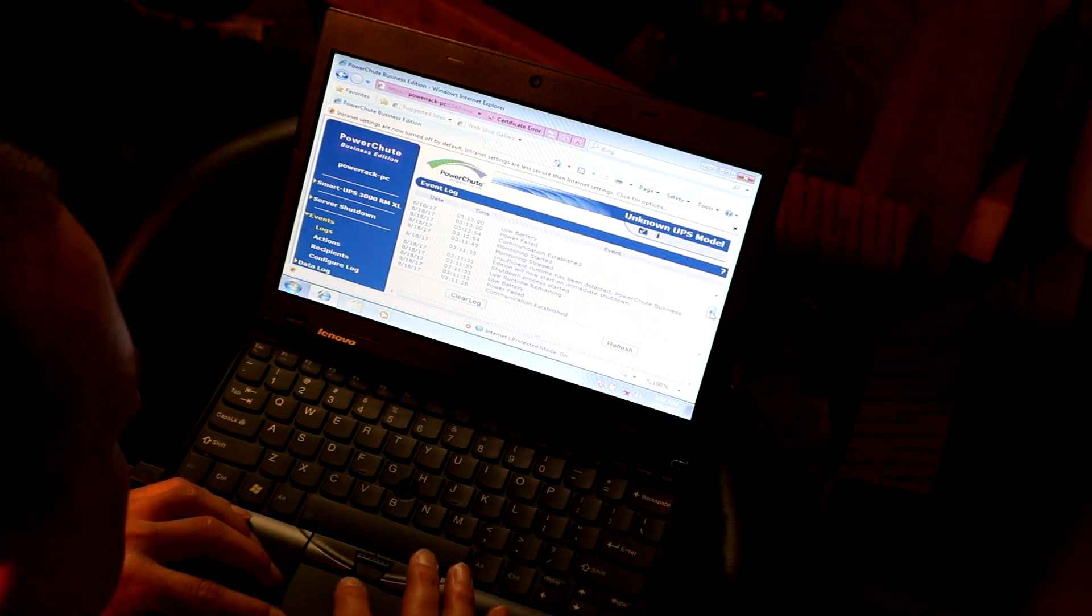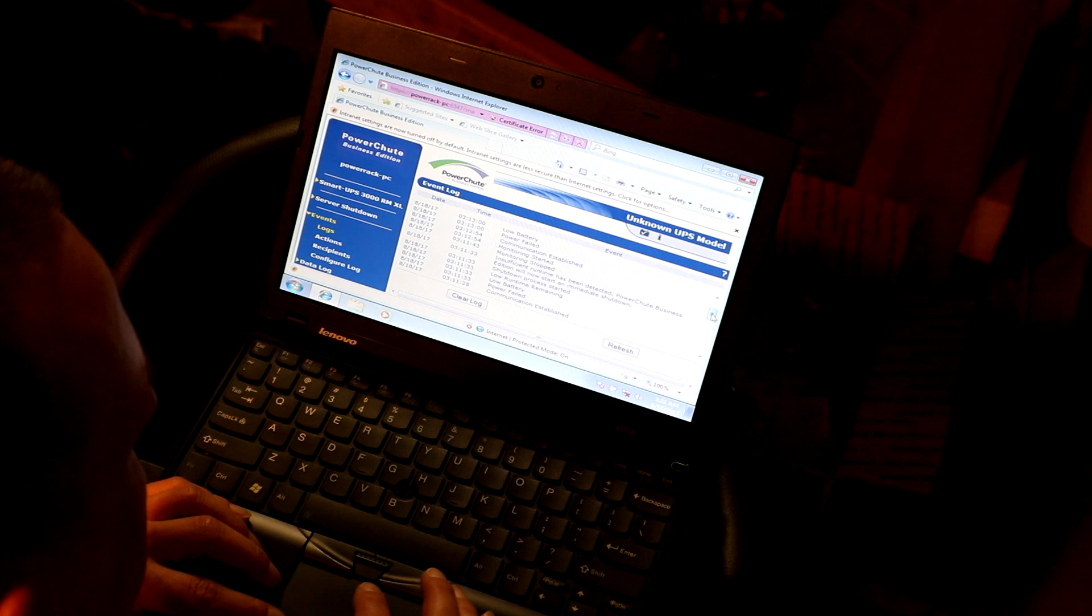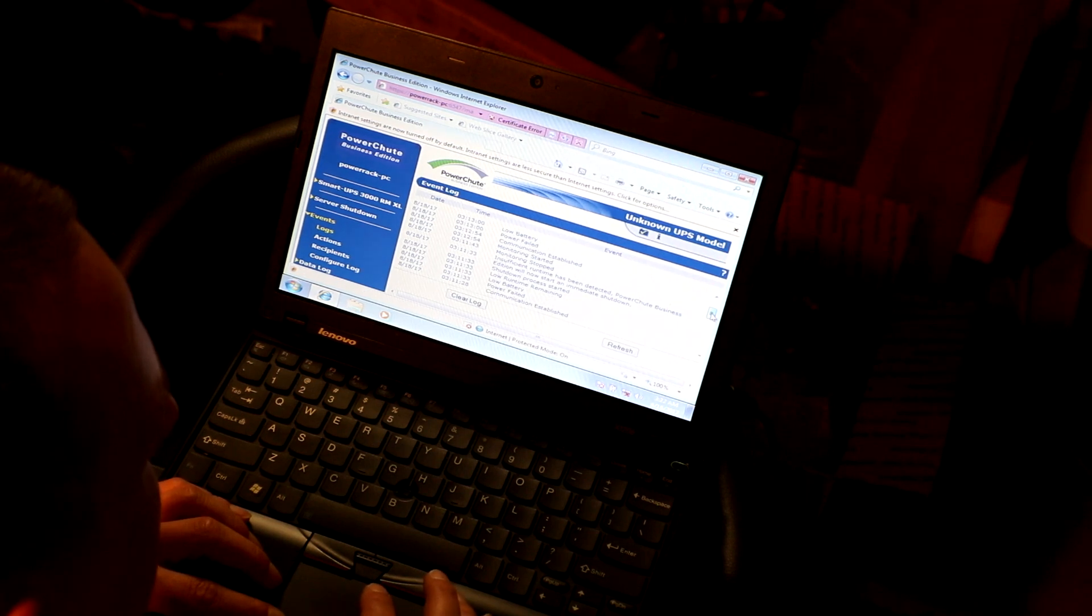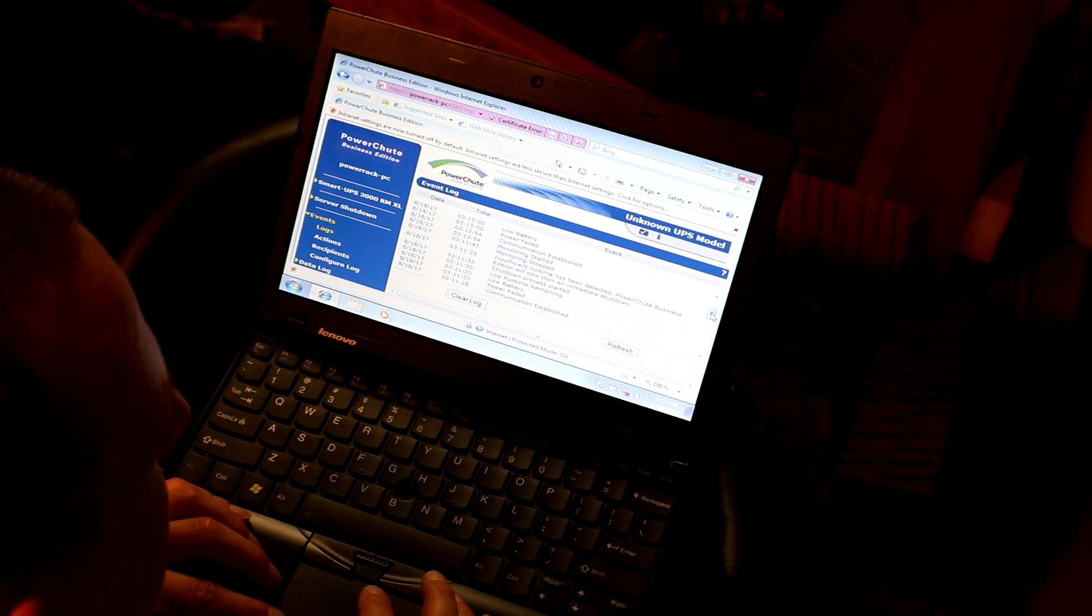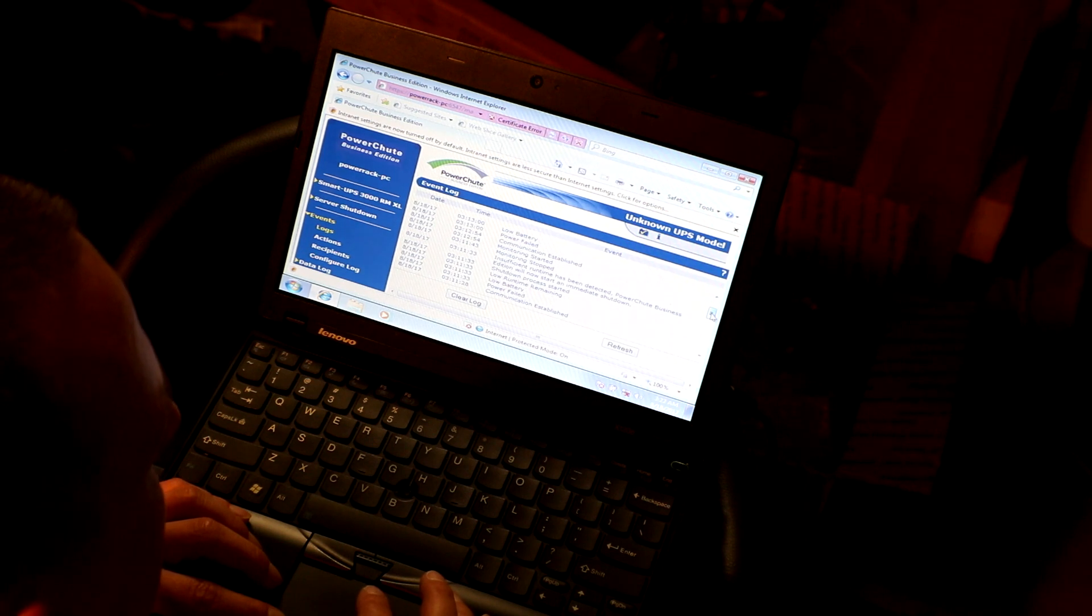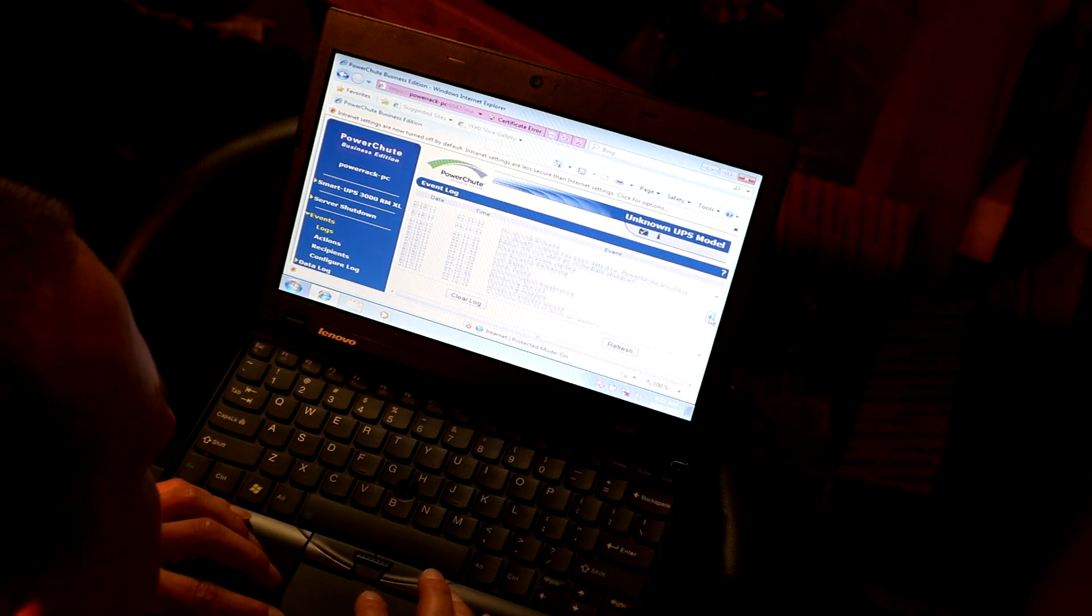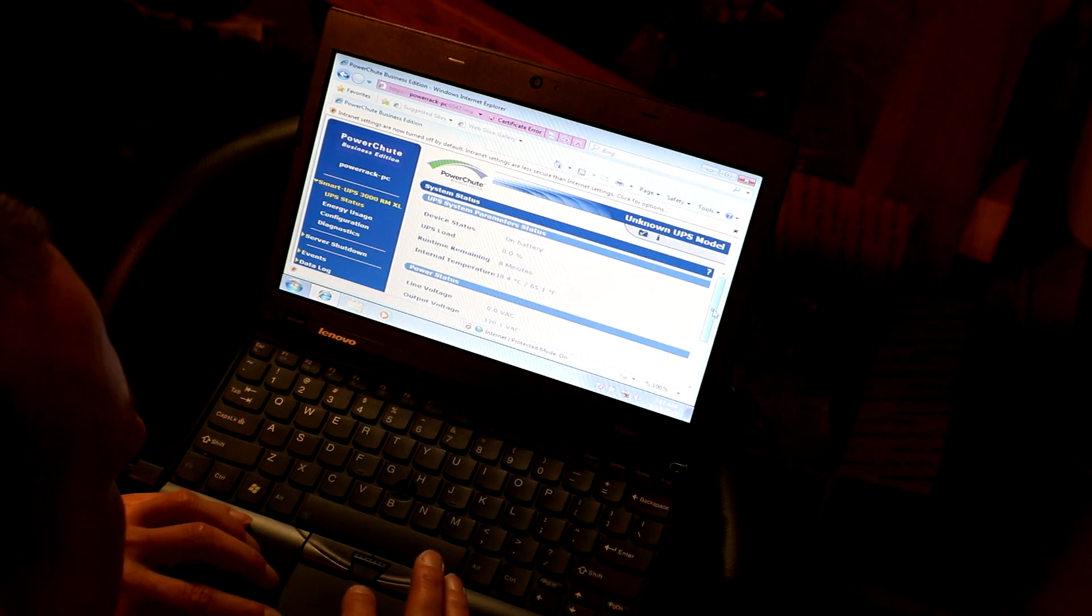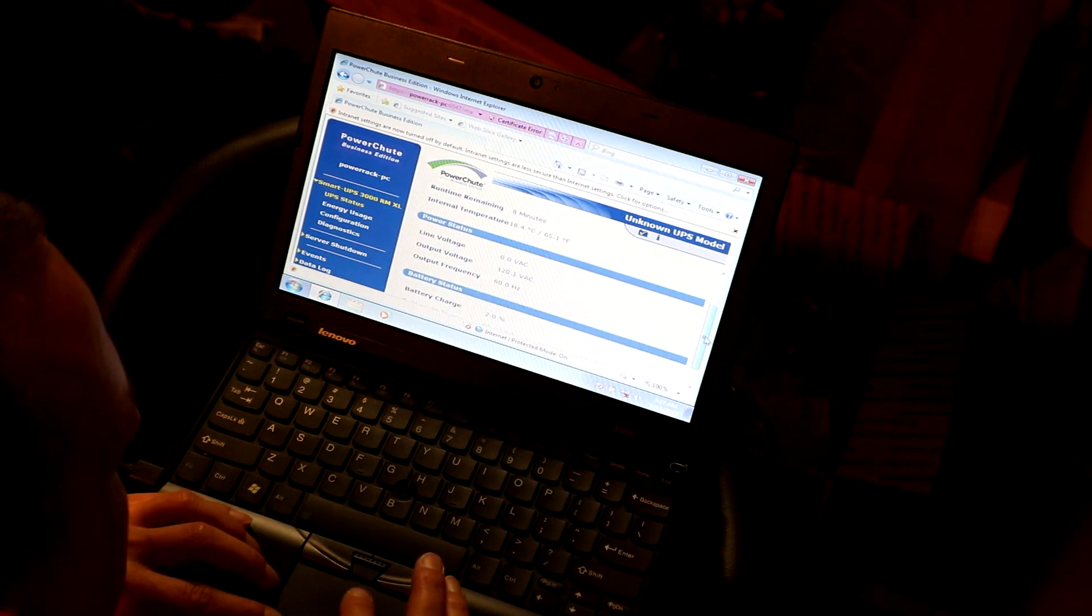Okay, so on here it says insufficient runtime has been detected. PowerChute Business Edition will now start an immediate shutdown. All right, so it thinks the battery died. There's got to be a way in here where I can change those settings.